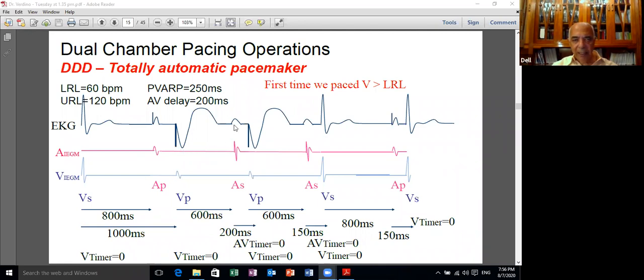And then we start to count 800 milliseconds to activate the atrium. But here an atrial event occurs. Whether this is a sinus beat or an atrial premature beat, it happened after 600 milliseconds. So it is sensed by the atrial electrode. It brings the AV clock to 0, and starts to count 200 milliseconds, which is the AV delay. Nothing is felt by the pacemaker, so it throws a spike and activates the ventricle. Now, after that, the VA timer is brought down to 0 and starts to count 800 milliseconds.